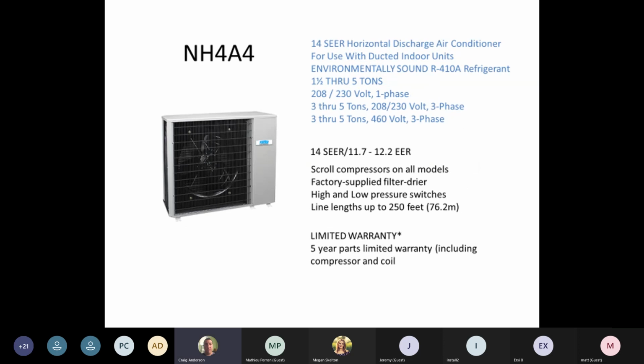NH4A4, so this is our side discharge unit. So for install purposes, we can get up to 250 feet of line length on this. So if we're doing condos, stuff like that, very nice unit, quiet. The funny thing is on this is when guys install these for the first time, I usually get a phone call. The fan motor on these, the way they're designed, this fan motor is designed to turn backwards. And it's a blow-through design on these units, the way they're manufactured. So I always get a call on a guy that's always installed it for the first time.